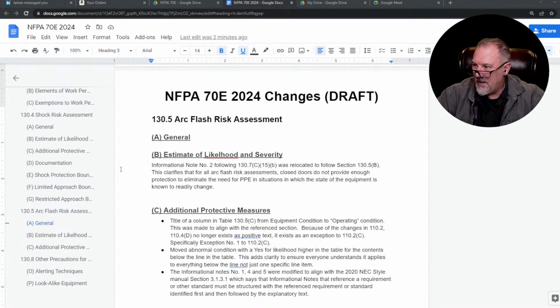All right, so they moved informational note number 2. So let's take a look. What is it? DC arc flash. 130.5 is arc flash risk assessment. No, hold on. Is it the informational note following the table? It's not the table, but the section. Yes, it's section B, which is direct current, DC equipment. That's the title of it.